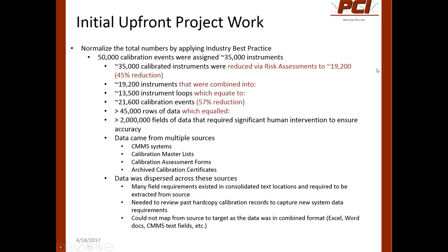There were many field requirements that existed in consolidated text locations. We needed to review past hard copy calibration records to capture the new system's data requirements. We just could not map from the source to a target because the data was not in the same format. For instance, in some of the CMMS systems, one of the fields was engineering units — and engineering units was spelled 19 different ways. Degrees C had the symbol for degrees with a capital C, and multiple other variations. So we could not do a direct data migration.